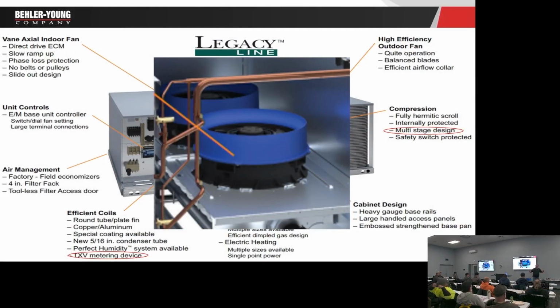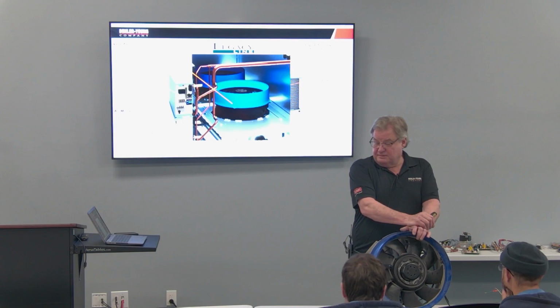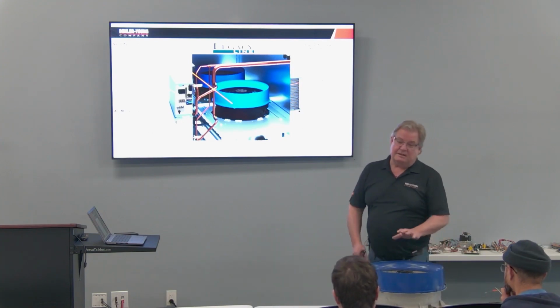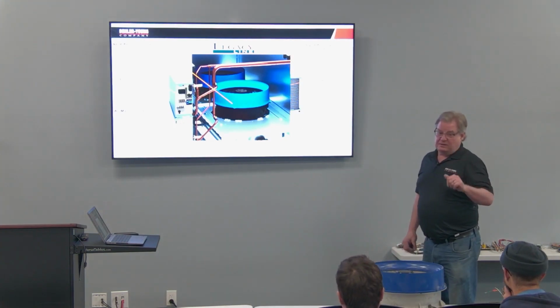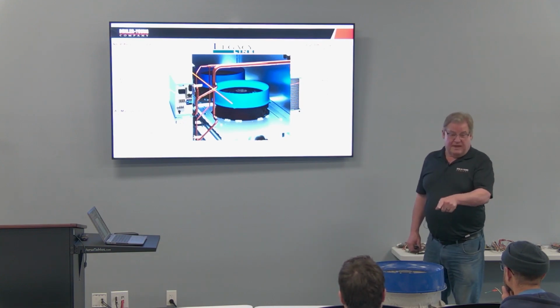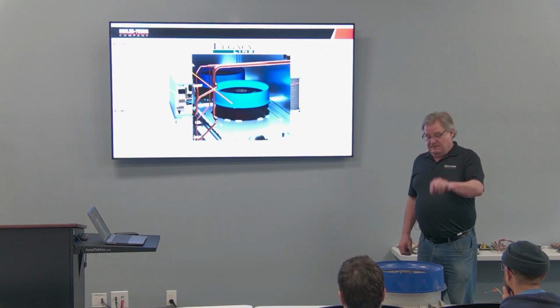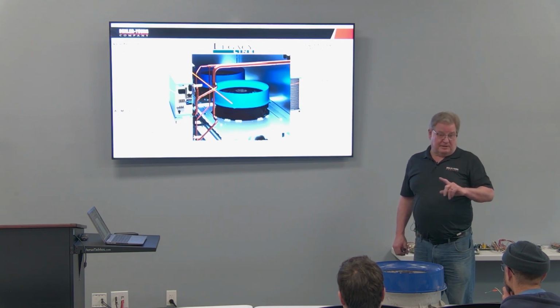Okay, so the big units, they come out in a tray. Now, anything over 6 ton, there's a safety circuit tied to these motors. So we'll see in a little bit where that safety circuit is at. Because these are sitting on top of the heat exchanger, they don't want this furnace to fire without this thing running, right? Because you're going to melt these blades. So there's a safety interlock on the 7.5 up to 27.5 ton unit. So if that motor fails, it's not an overload, it's a safety circuit. If the electronics in that motor fail, it's going to open a switch, which will stop the unit from coming on.